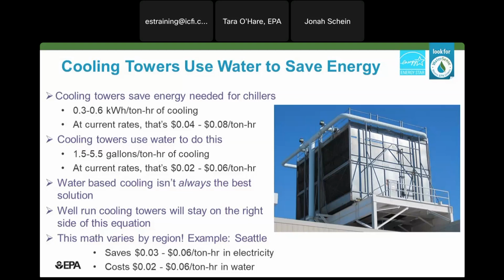I think for a lot of years there was this default to assume that yes, at a certain size of building, it automatically was, but I don't know that that's always the case. And if we put numbers to it, cooling towers compared to air-cooled equipment tend to save somewhere between 0.3 and 0.6 kilowatt hours per ton hour of cooling, which adds up a lot. If you have a big facility and a lot of cooling load, you have a lot of ton hours. 0.3, 0.6 kilowatt hours per ton hour of cooling can be quite significant. At current average national commercial electric rates, that's about 4 to 8 cents per ton hour of cost savings.